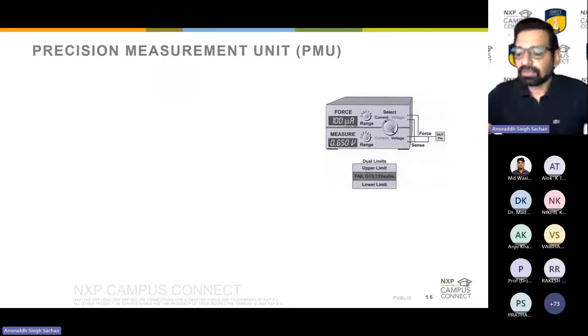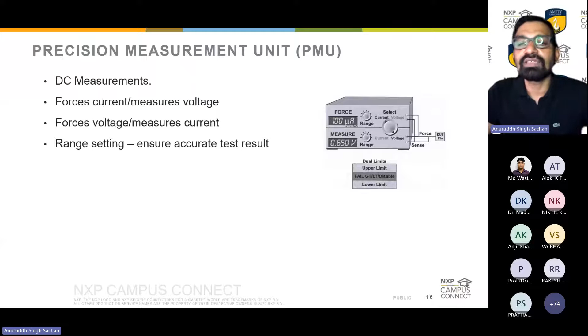Range setting ensures accurate test results. You can have multiple ranges. If testing an SOC with lower voltage, select a lower range which has more accuracy. If testing with 5 volts, select a higher range. So it has various ranges, and you select based on the accuracy you need for that voltage or current.